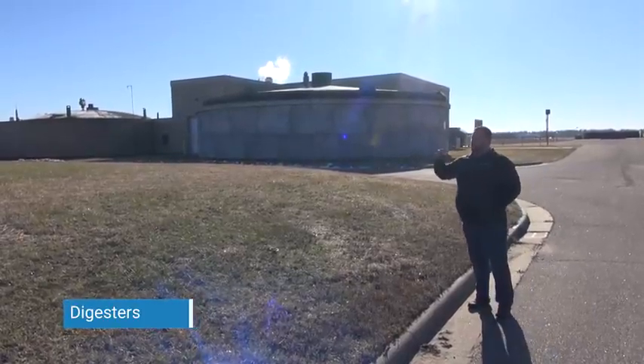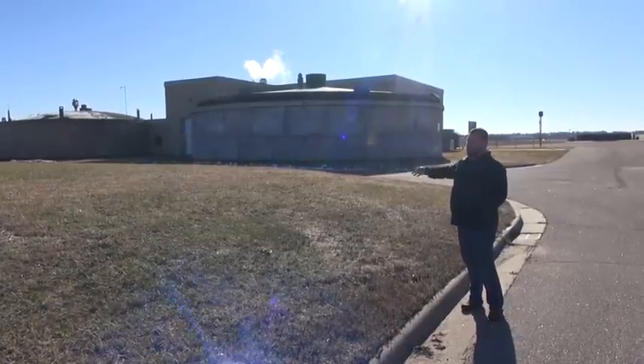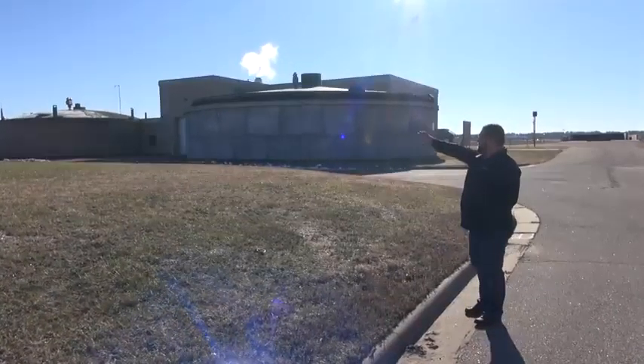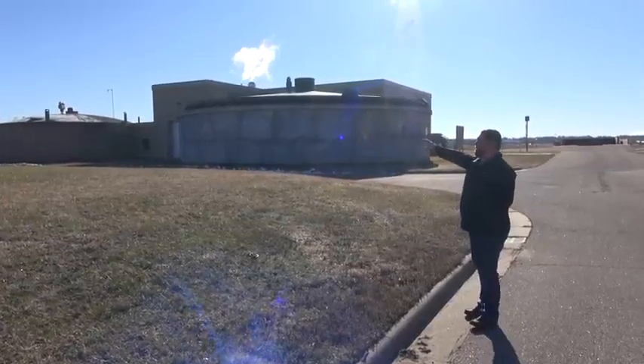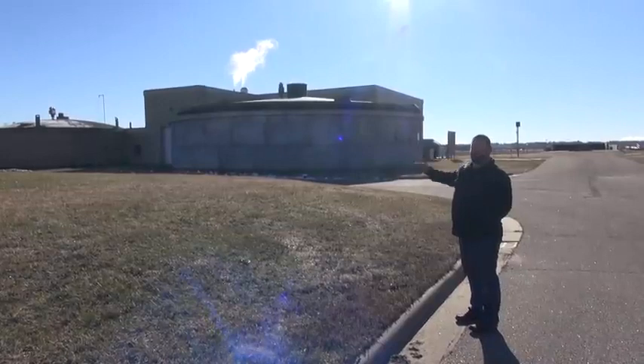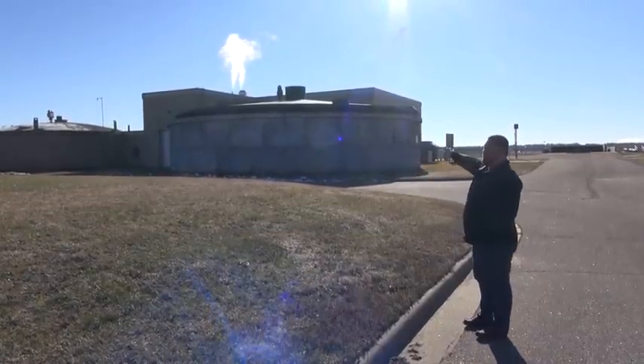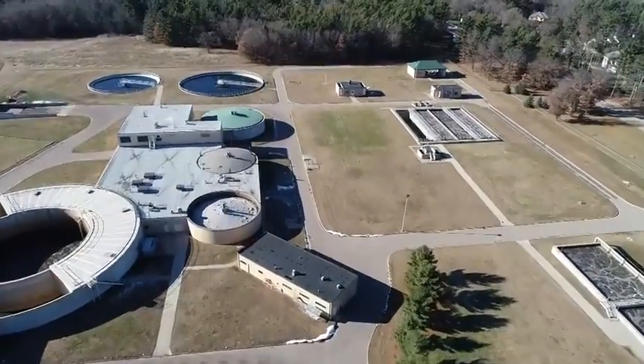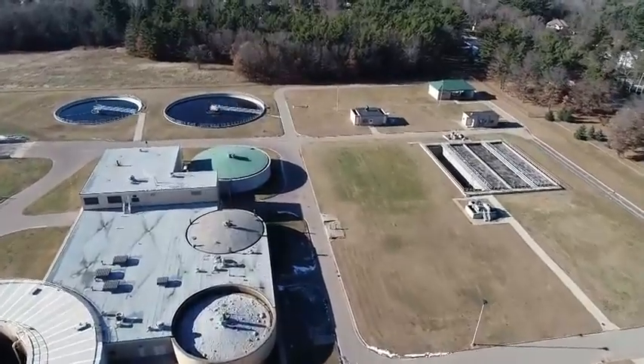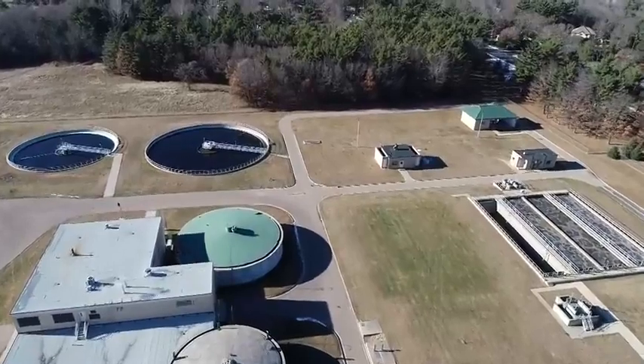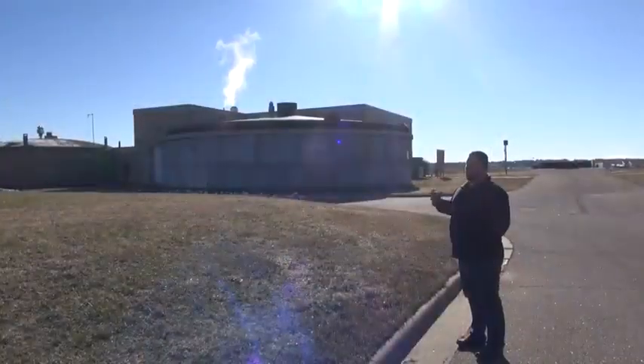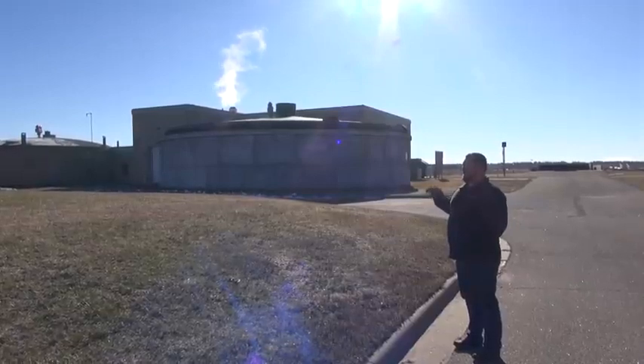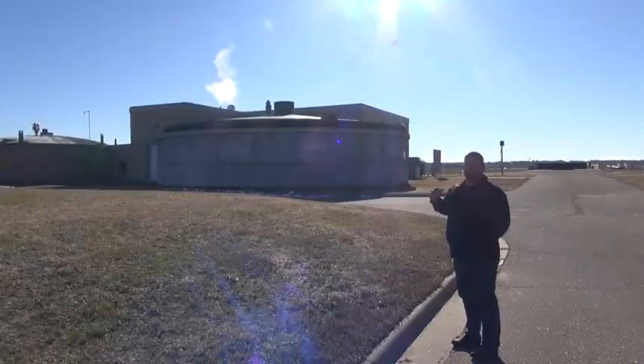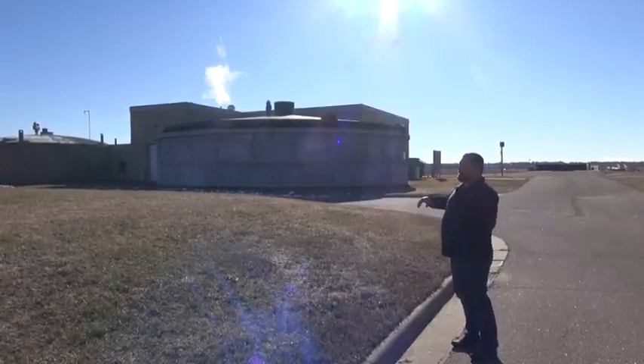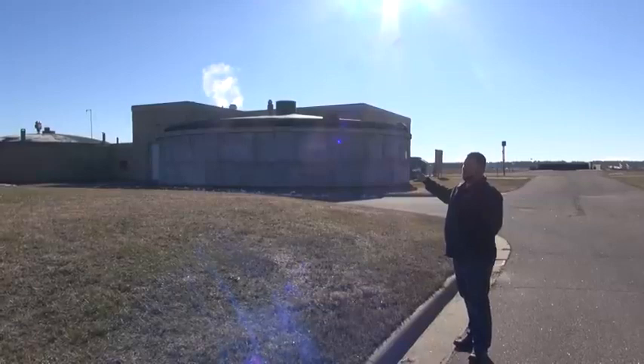And the whole time we were talking about solids that settle after we pump to the digesters, and that's what we're talking about here. We have 3 different digesters, all anaerobic. 2 of them are thermophilic digesters, which means they're heated to 131 degrees Fahrenheit. This larger last step is like a secondary digester, and that's a mesophilic, so that's only heated to about 98 degrees Fahrenheit. And what you're doing in these digesters is you're pumping in those solids we talked about, those volatile organic solids. You're creating an anaerobic condition, you're heating it, and you're mixing it, and it's no more complicated than that. And in that anaerobic heated condition, you have anaerobic bacteria that starts to grow, and they're consuming the volatile organics.